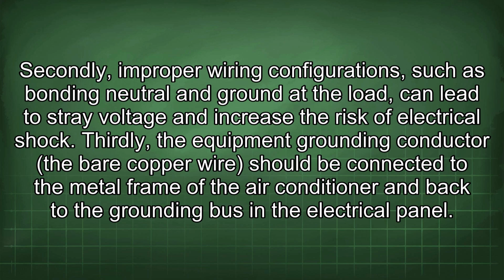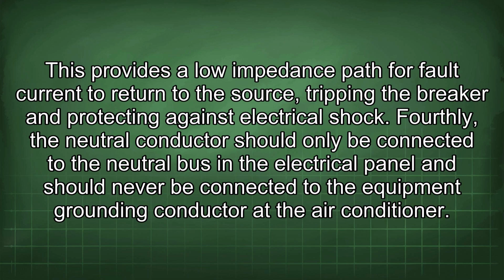Thirdly, the equipment grounding conductor, the bare copper wire, should be connected to the metal frame of the air conditioner and back to the grounding bus in the electrical panel. This provides a low impedance path for fault current to return to the source, tripping the breaker and protecting against electrical shock. Fourthly, the neutral conductor should only be connected to the neutral bus in the electrical panel and should never be connected to the equipment grounding conductor at the air conditioner.